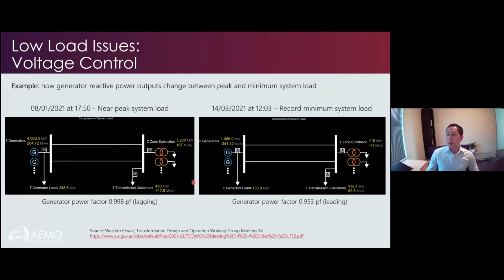Now, you compare this to the minimum load day, which is on the 14th of March. So this is our record minimum load day at the moment. Now the loads themselves are injecting VARs, and also the generators are now absorbing a lot of VARs. So you can see here the difference between a peak and a minimum load day. And as you get less and less generation, you probably still have to absorb the same amount of VARs, but you have less generators doing it. And that's probably where some of the issues are occurring.